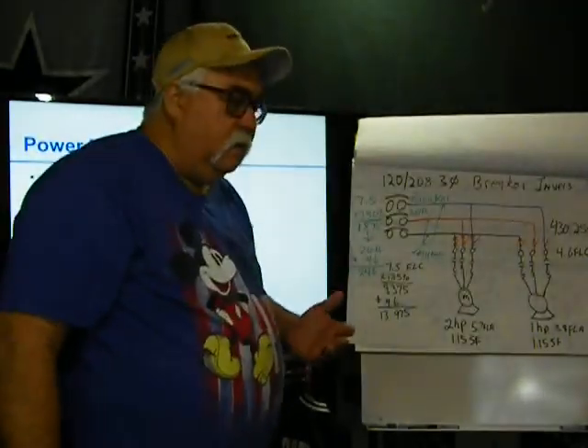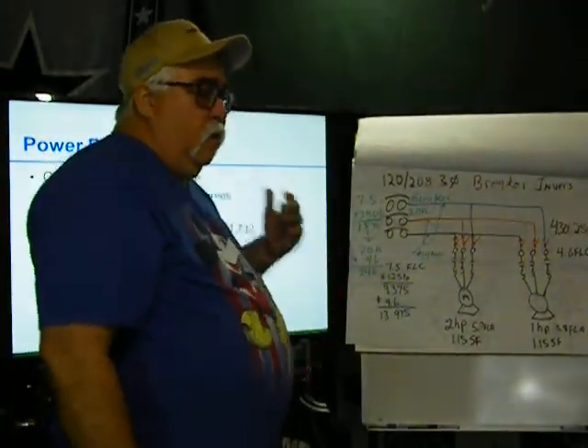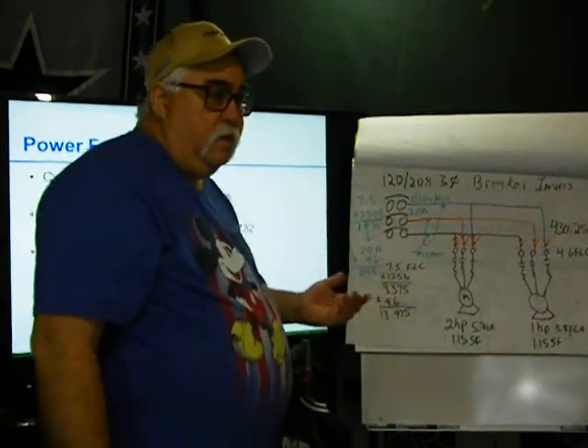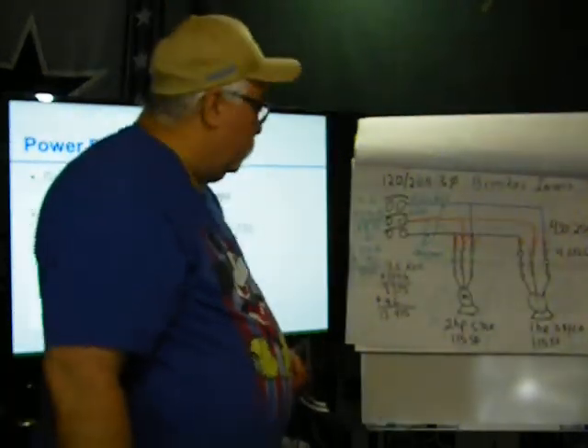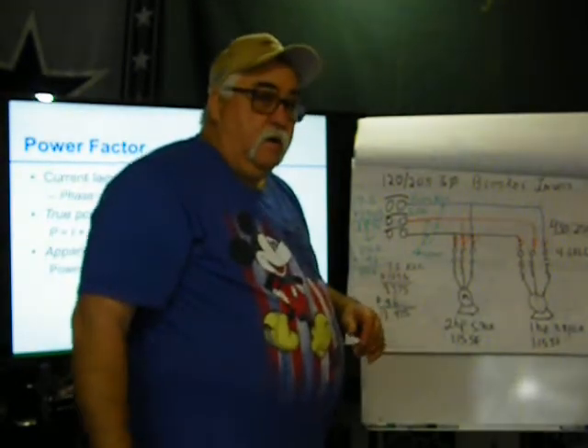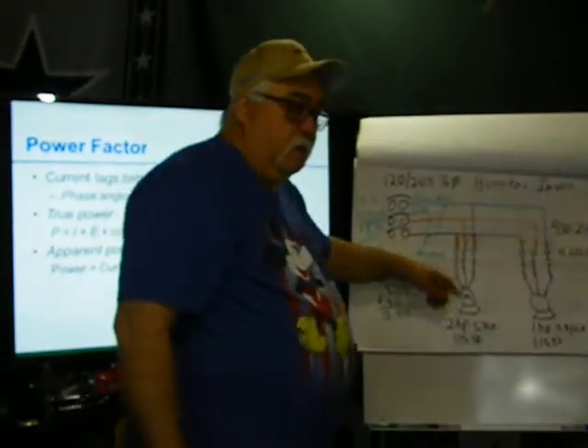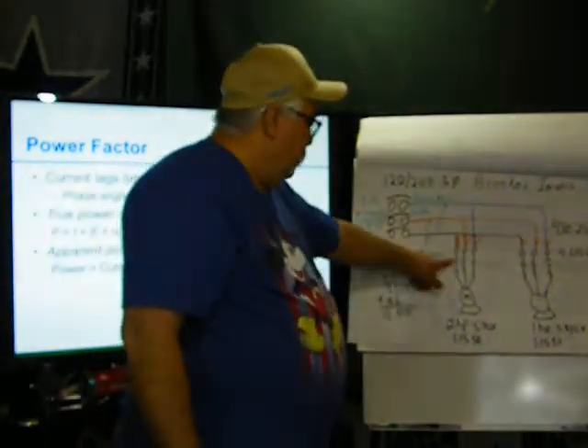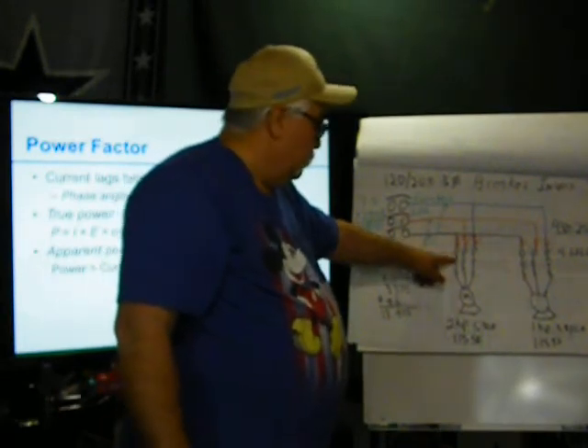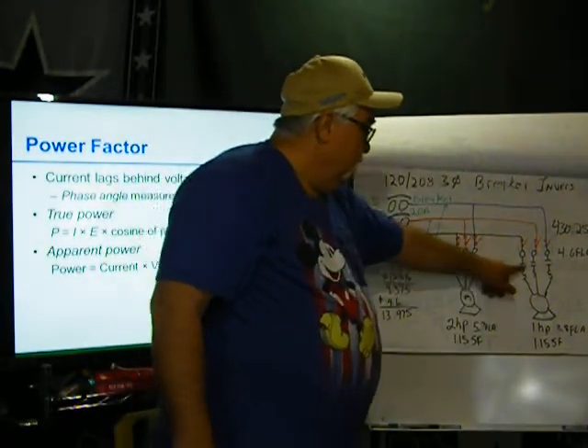It's not called an overload. It's not called overcurrent protection because it's not against overcurrent. It's against short circuit and ground faults. Our overloads, our overcurrent protection, is right here in our overloads, because this is going to be sized to protect that motor. These are going to be sized to protect that motor.